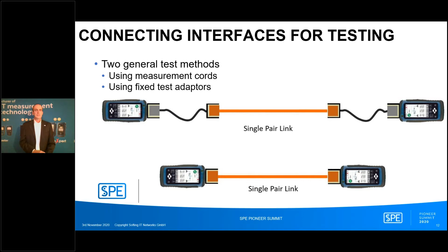The advantage of the upper one, when you use measurement cords, is that it's easier to adapt to another connector. But the disadvantage, of course, is that we have a measurement cord that must not influence the measurements. So somehow the tester has to remove that cord from the measurement. That is, from a mathematical point of view, quite a challenge, but doable. So some testers on the market do this. The other method is, of course, you can connect directly to the tester. The advantage here is it's much easier for the tester because there's no measurement cord that needs to be removed. The disadvantage is you have to develop lots of different-style test adapters for it. So both deliver equally good or bad results, but both have advantages and disadvantages. It's up to the user to decide which one to use.